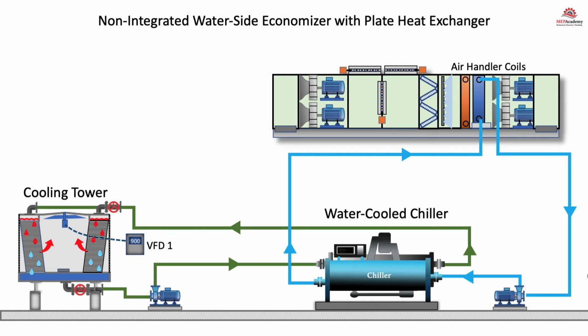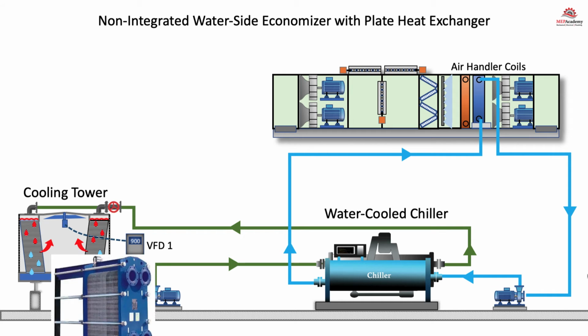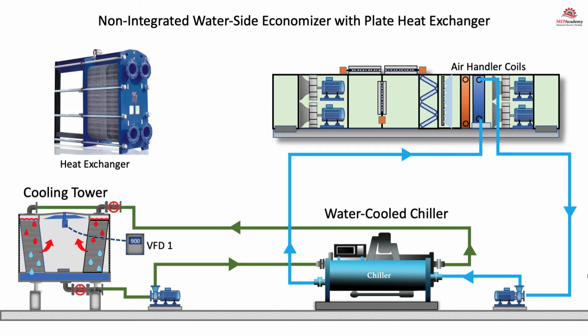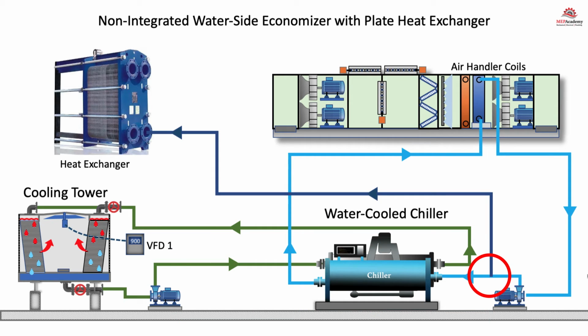We install a plate and frame heat exchanger and then tap into the chilled water return piping and connect to the inlet on the warm side of the heat exchanger. From the outlet on the warm side of the heat exchanger, we connect into the chilled water supply, feeding the load in the building. In this case, we show one air handler, but this could be dozens of air handlers.